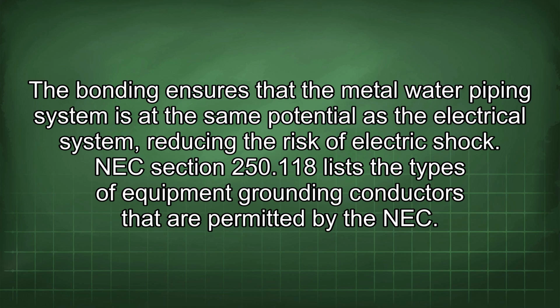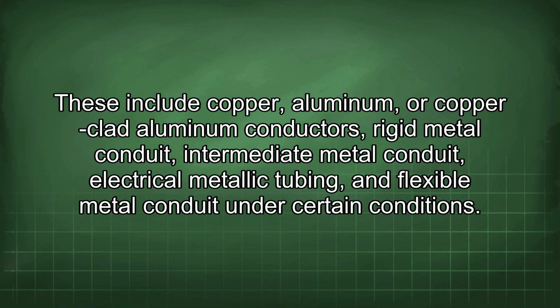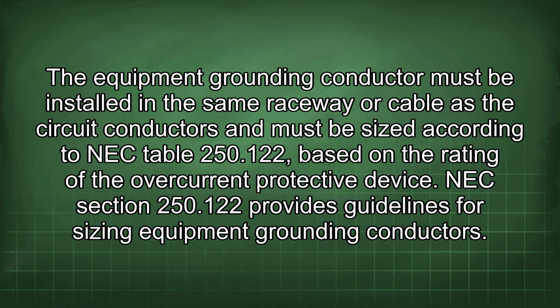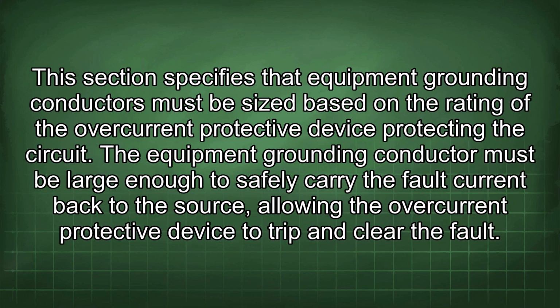NEC section 250.118 lists the types of equipment grounding conductors that are permitted by the NEC. These include copper, aluminum, or copper-clad aluminum conductors, rigid metal conduit, intermediate metal conduit, electrical metallic tubing, and flexible metal conduit under certain conditions. The equipment grounding conductor must be installed in the same raceway or cable as the circuit conductors and must be sized according to NEC Table 250.122 based on the rating of the overcurrent protective device. NEC section 250.122 provides guidelines for sizing equipment grounding conductors. This section specifies that equipment grounding conductors must be sized based on the rating of the overcurrent protective device protecting the circuit.